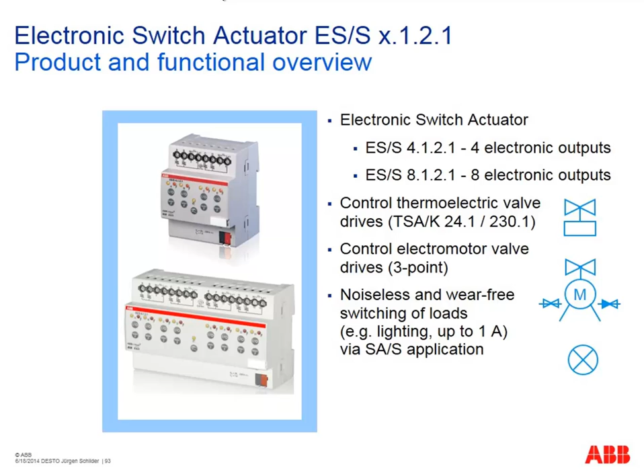You will find this in this electronic switch actuator, but not only, other devices as well. So we can control electrothermal valve drives, motor valve drives, but additionally, if you want, you can use it also as a normal switching application to operate any lamp loads, for example. But be careful, only up to 1 ampere. So the nominal current of one electronic output is normally lower than a mechanical output. But with a load up to 1 ampere nominal current, you can operate this as a normal switch actuator output. It's possible. So it's a special additional application here.